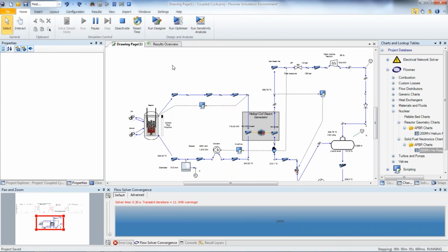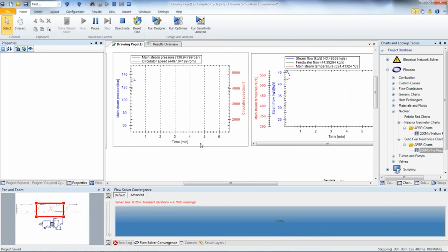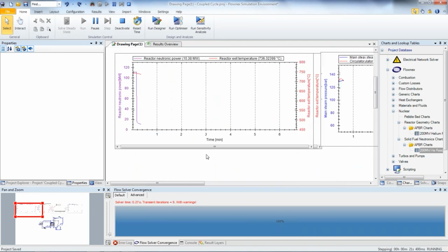We're able to see the network runs for a few seconds in its normal conditions, and then you see the control rods drop to their lowest position with the reactor scram. At this moment, the valve is open, and we have some of our primary coolant leaking out. I've put together a couple of graphs to try and illustrate what's happening at the moment.